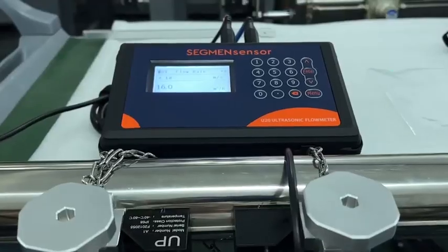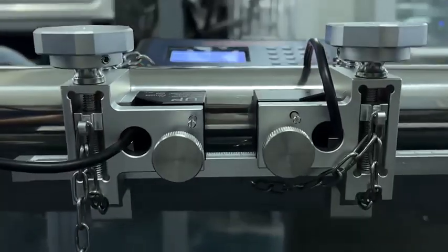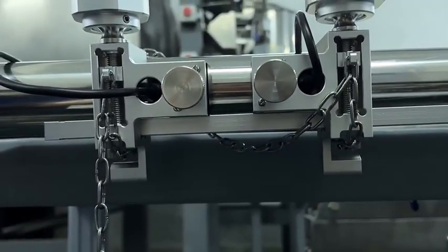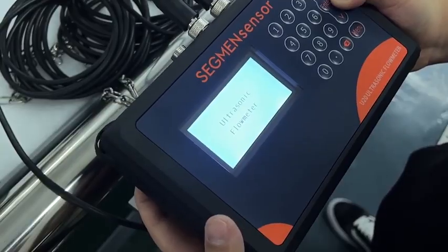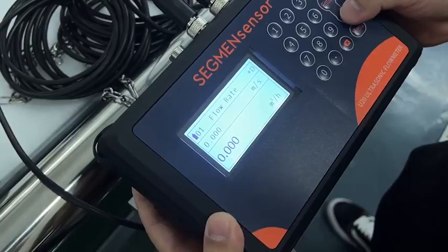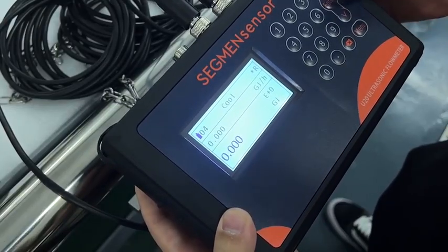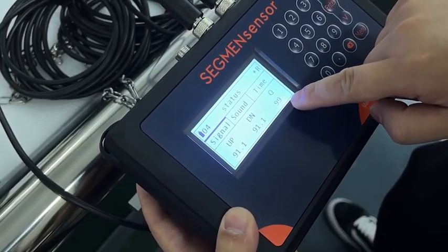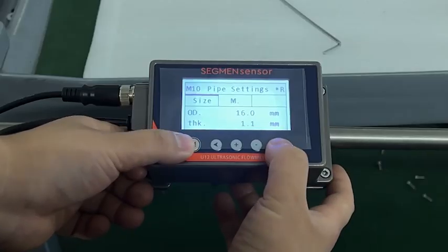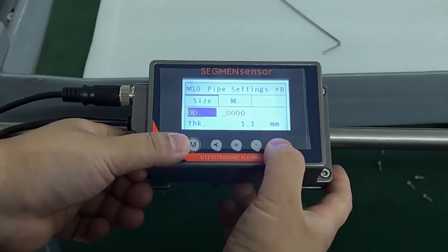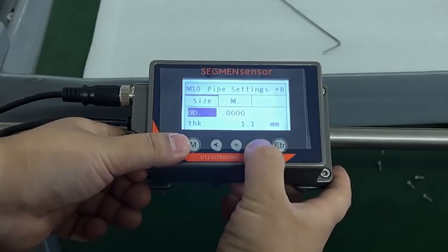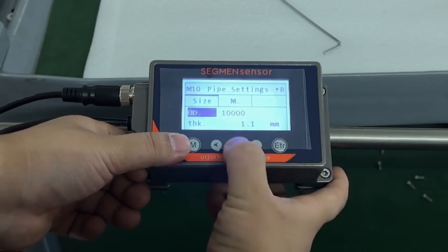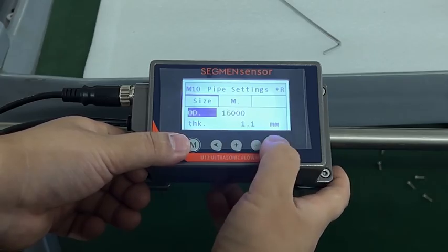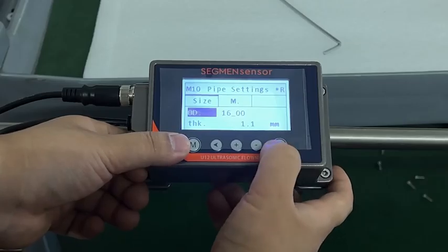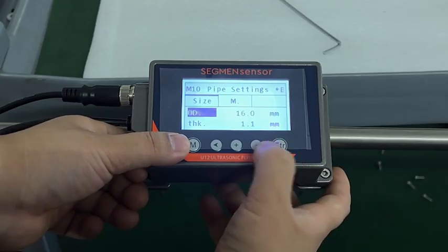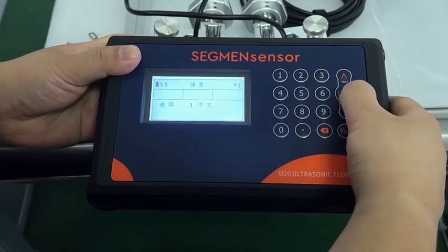With the sensor assembly fully installed on the calibration pipe, the transmitter is powered on. The unit initializes, runs a self-diagnostic check, and begins searching for an ultrasonic signal through the pipe wall. Signal acquisition typically takes less than 5 seconds on clean metallic pipes with properly applied coupling gel. The engineer now enters the pipe parameters into the transmitter. Outer diameter, wall thickness, pipe material, and fluid type are all entered via the keypad. The transmitter uses these values to calculate the speed of sound in the pipe wall, determine the time of flight path length, and configure the internal signal processing for this specific installation.